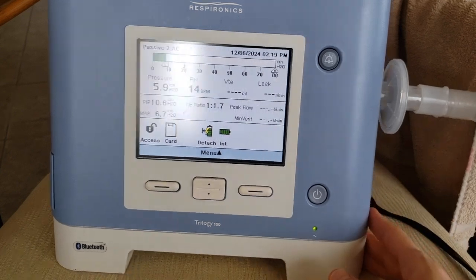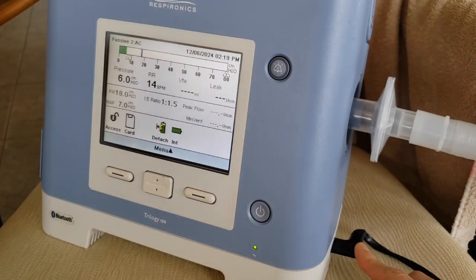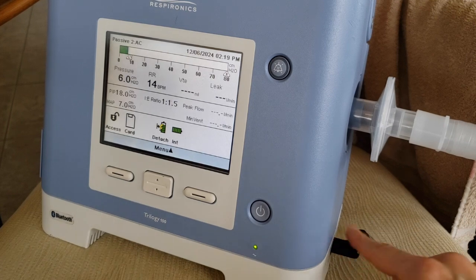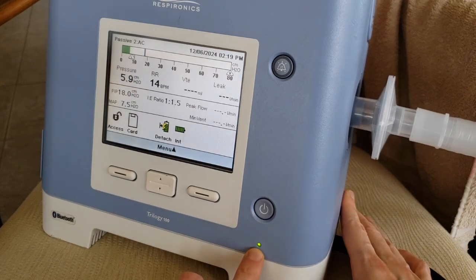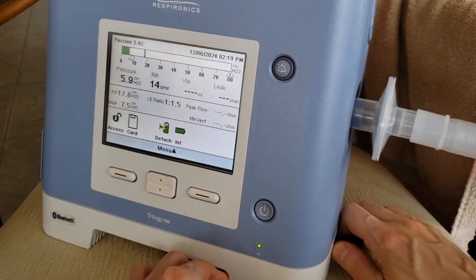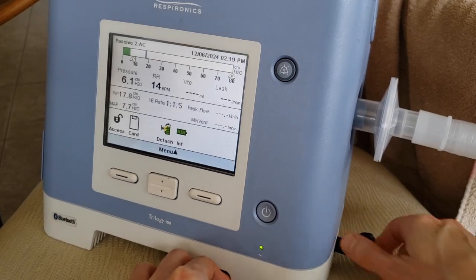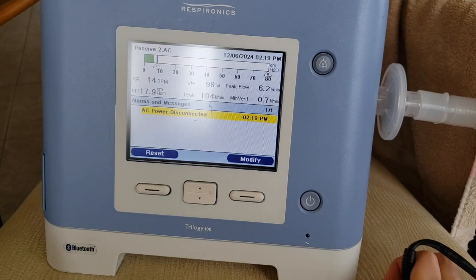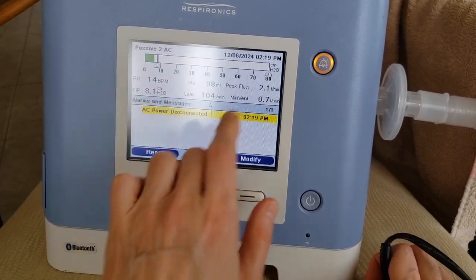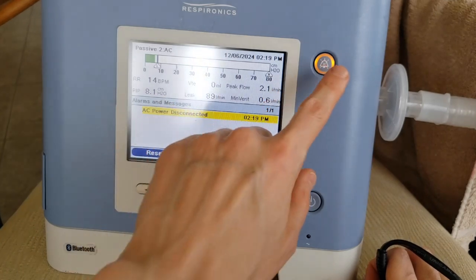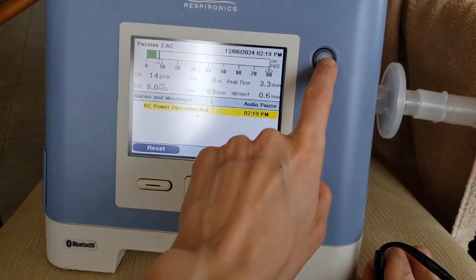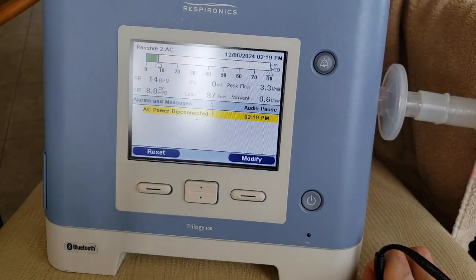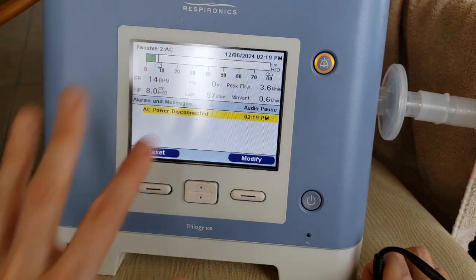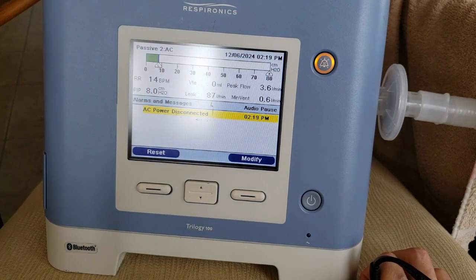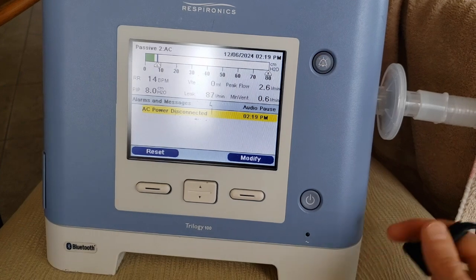There's also an outlet that this can be plugged into. When it's plugged in, this is green. When I unplug this, this is going to alarm to let us know that it is not plugged in. And now you're going to get an alarm, and this is going to beep on you. To get rid of this alarm, you can silence it, but that will continue. This will continue to flash an alarm for the next 2 minutes if you do nothing, or unless you plug this back in.